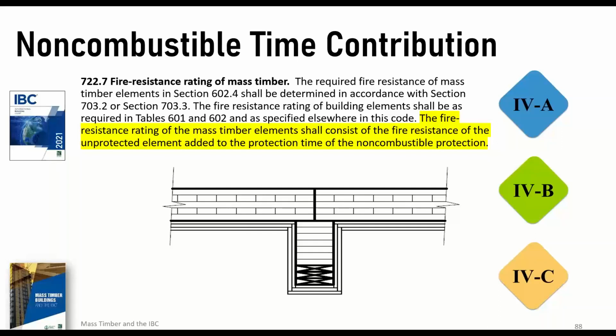So in the detail we have shown here, we're showing what was probably a type 4A detail. So we have 3 layers of hopefully 5/8 type X gypsum wallboard. You can see we're lapping the corners, and we'll get into that a little bit more in detail. But we want to take the time attributable to the non-combustible gypsum and then add that layer of protection to delay the negative effects of fire and combustion that the CLT or mass timber would be subjected to if it wasn't protected by the gypsum.